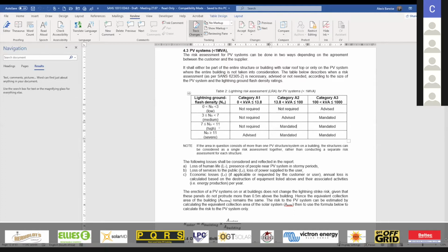When we get to a lightning flash density above 7 - areas like Bloemfontein, the Vaal, Heilbron, all the way to 11 which is Pretoria - then it becomes mandated, an absolute requirement that a risk assessment be done at the time of design and execution of the project.